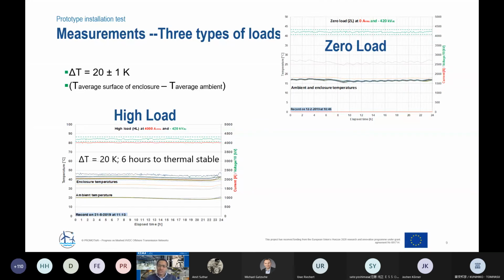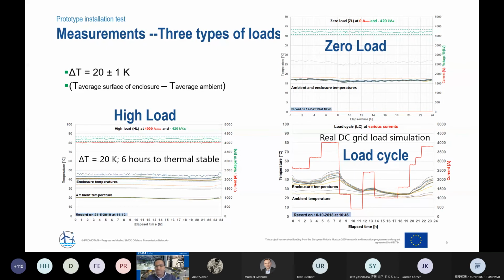Of course, we have applied 20% more than the rated continuous voltage to take into account some aging aspects as well. The load cycle I was mentioning, which is more realistic, as the power flow in the system changes during the day. This is a typical day where at some hours of the day it's fully loaded, and in some cases it's really low loaded. So that's why you also see the enclosure temperature following the loading of the bus bars.